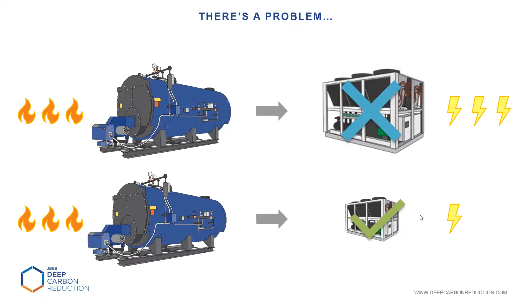So the fundamental problem we have when doing a like-for-like swap with an existing building, or even new construction, when we do our heating load calculations, is that we always want one piece of equipment to meet the entire load and move on. When we look to do an electrified swap with mostly an air source heat pump solution, that's a real challenge physically, because those heat pumps require outdoor airspace access.